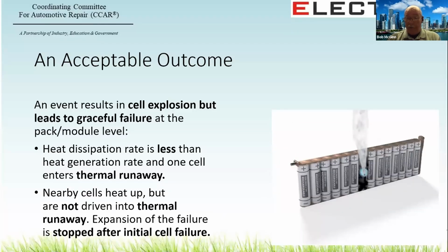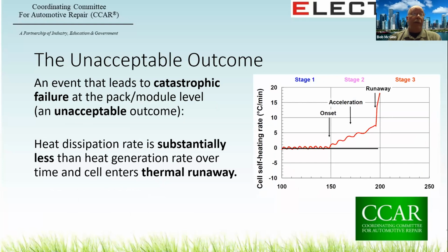To recap, an event occurs within the cell that causes an increase in temperature, be it a short circuit, adjacent heating, overcharge, whatever it is that causes the cell to fail. Reaction within the cell creates additional heat and gas. The reaction zone expands. Dissipation rate is less than the heat generation rate, and the cell enters thermal runaway. As additional heat and gas are produced, the cell vents and explodes. But we do not take nearby cells with us, which leaves us with the unacceptable outcome. And if you remember a little earlier, I said that about 170 or so to 190 degrees is the magic number to trip the trigger for a thermal runaway.